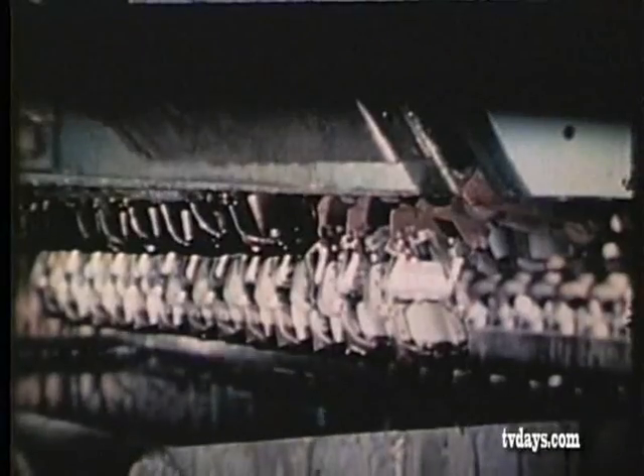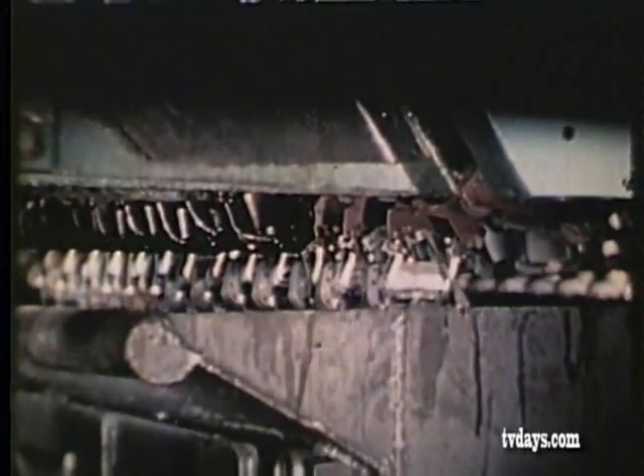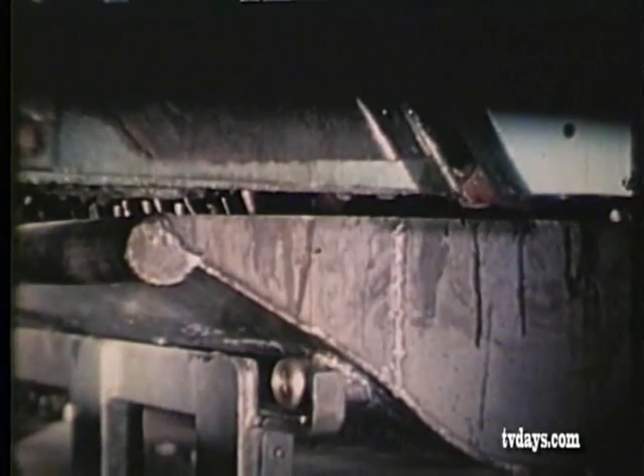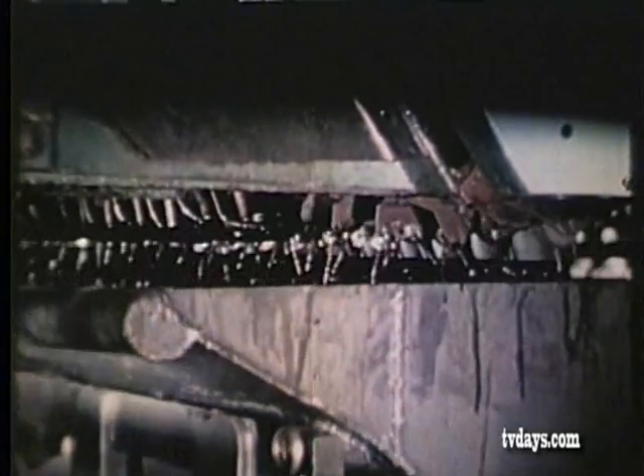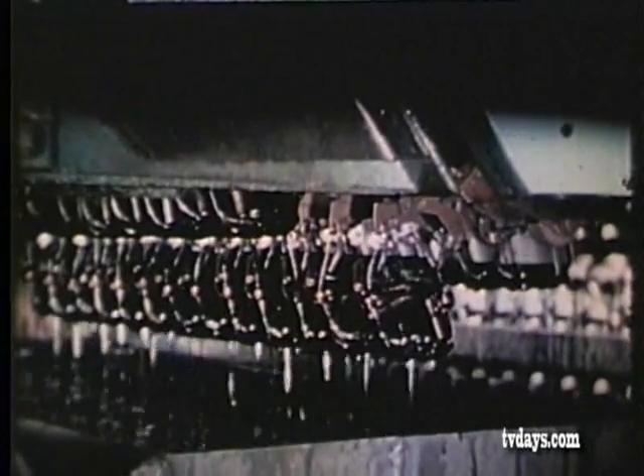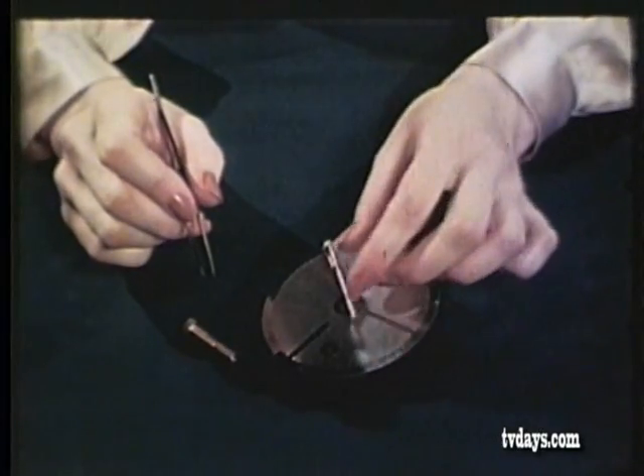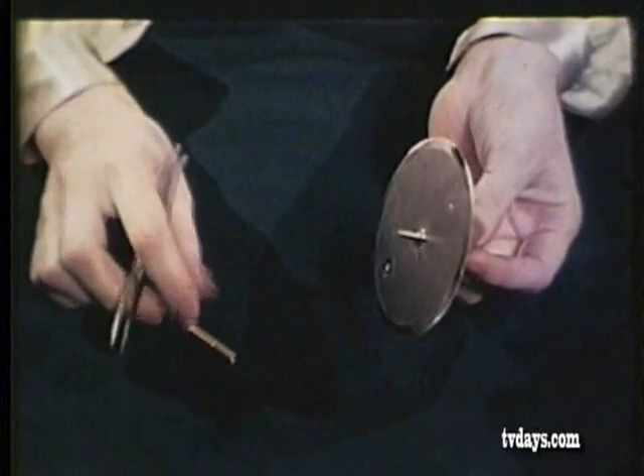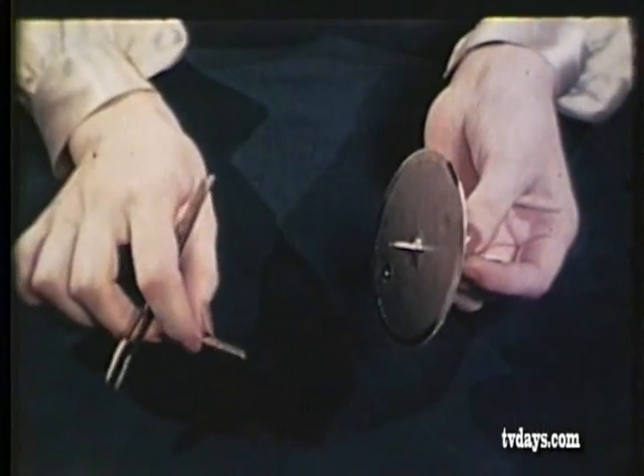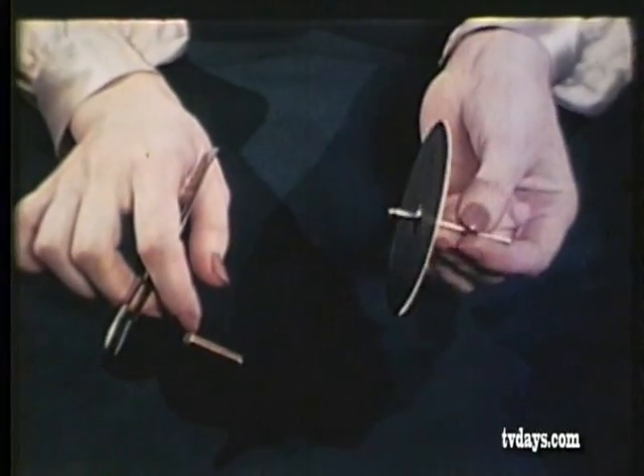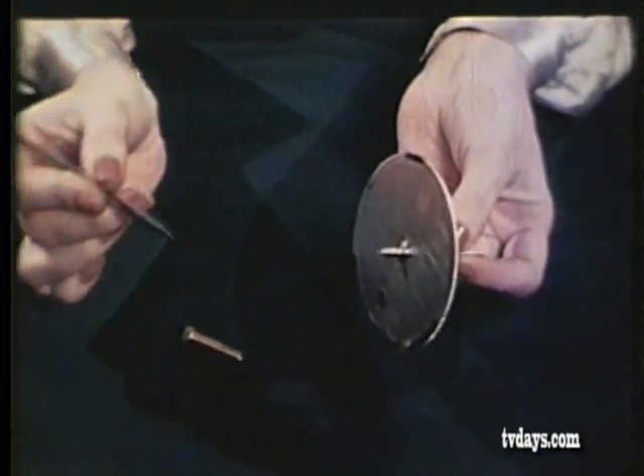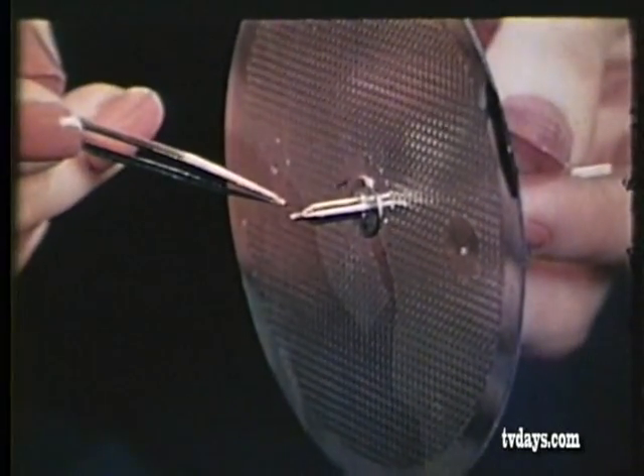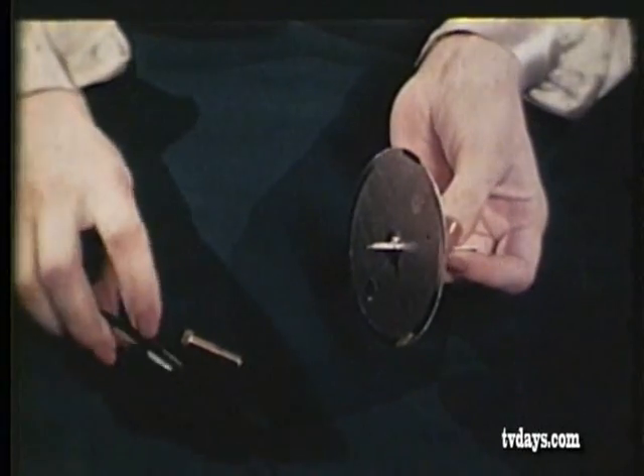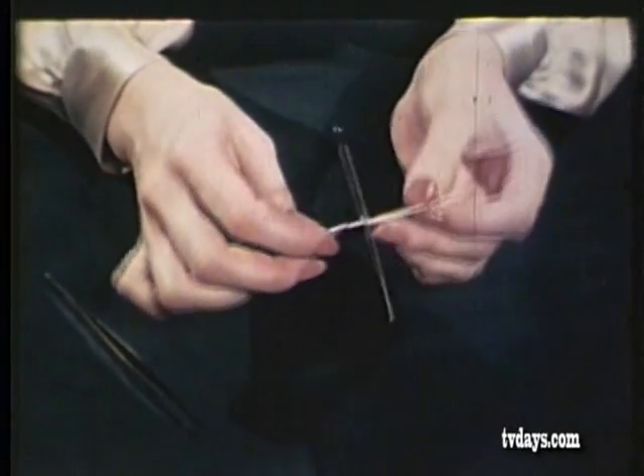After a preliminary inspection, the electric elements are impregnated with an insulating varnish and placed in an oven to bake for several hours. While they're baking, let's look in on some other phases of meter construction. The shaft and disc and bearing assembly, for instance. The rotating element is extremely light in construction, yet when its weight is concentrated on the tiny, rounded pivot of cobalt tungsten, the pressure exerted on the jewel is equal to 70 tons per square inch.